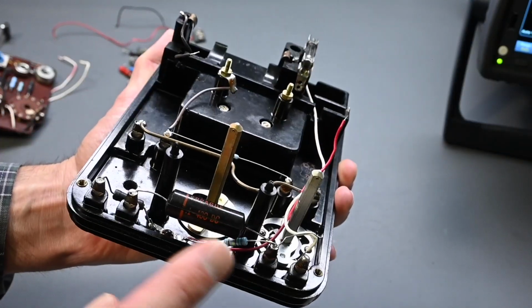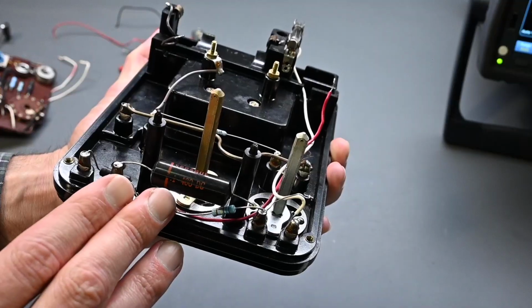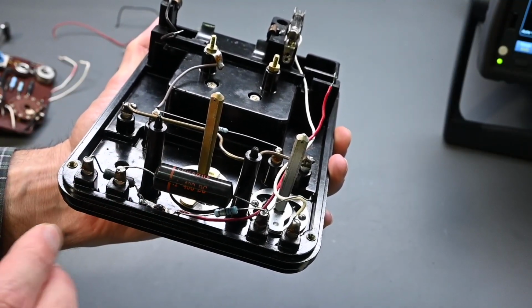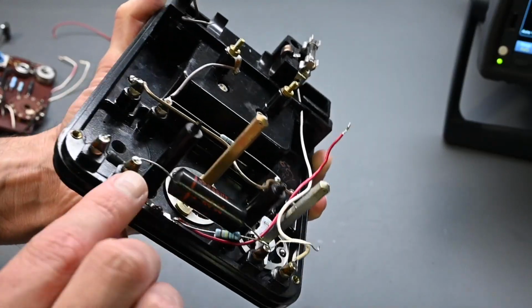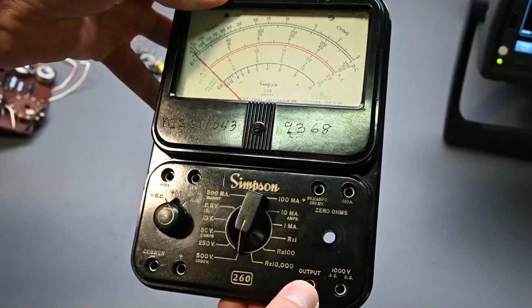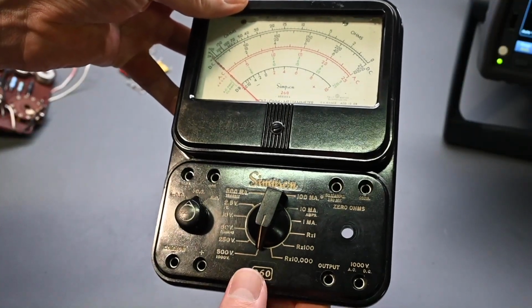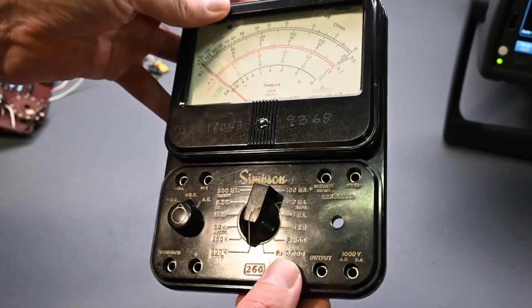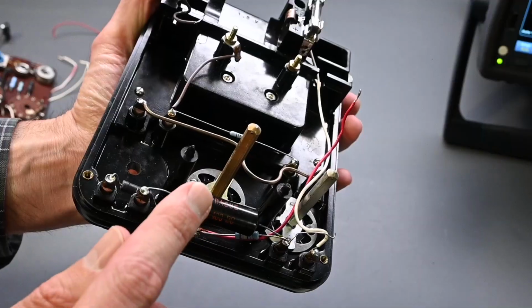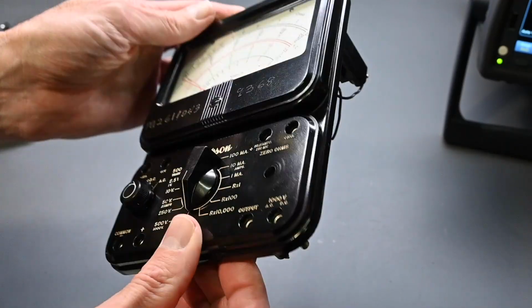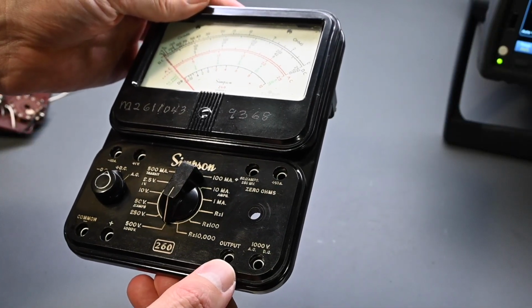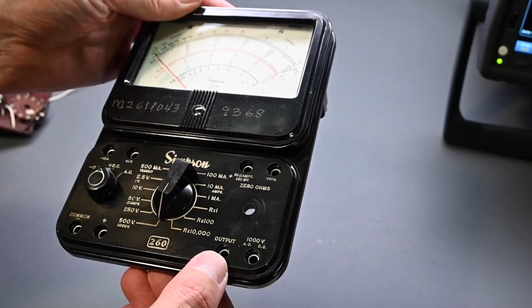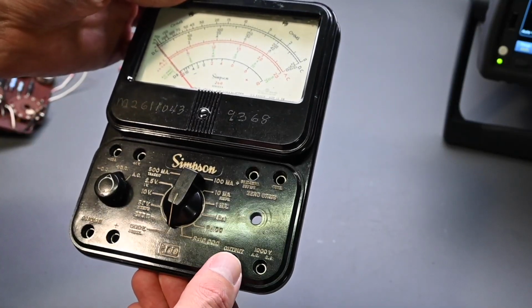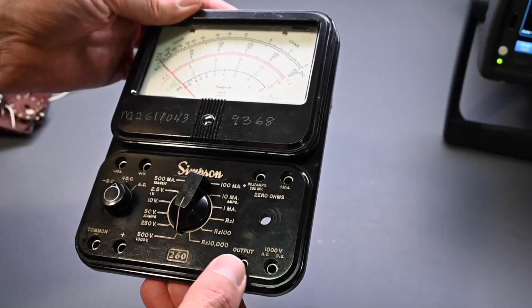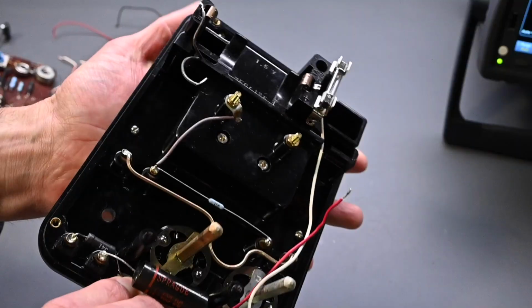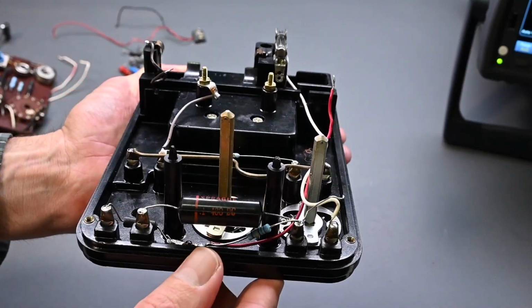Also, the purpose of this capacitor in the meter is for measurements where you have an AC voltage riding on a DC voltage, and you want to block the DC voltage. If you look at the front panel, this attaches to two terminals. One terminal is marked as output, and then it goes over here to the positive input. So it's just bridged across those terminals. If you connect to the output terminal right here, your signal goes through this capacitor, and any DC voltage is blocked and AC voltage passes through. The reason it says output is because it's intended to connect to maybe an instrument or an amplifier where you're measuring the output signal, and you would have that DC voltage with an AC voltage. So this output doesn't mean there's a signal coming out of this terminal. Again, this is an input for what you're measuring. We'll get back to the capacitor tester and I'll show you how this is testing in just a moment.